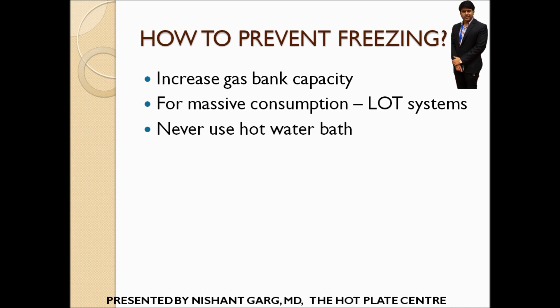Now, what are the measures that should be adopted to prevent cylinder freezing? First of all, we can increase the gas bank capacity. When we increase the gas bank capacity, the supply side increases, and by increasing the supply side we automatically lower the heat extraction rate of the liquid LPG present inside the cylinder.